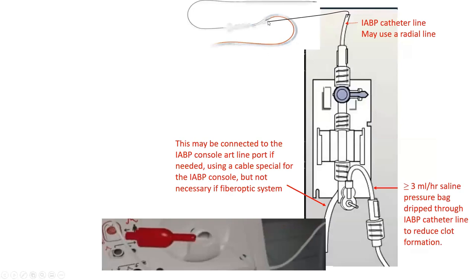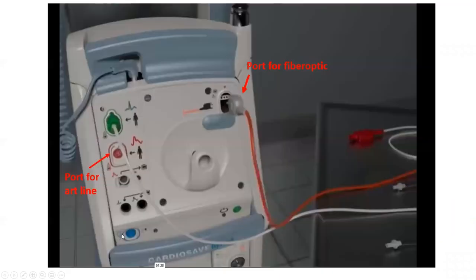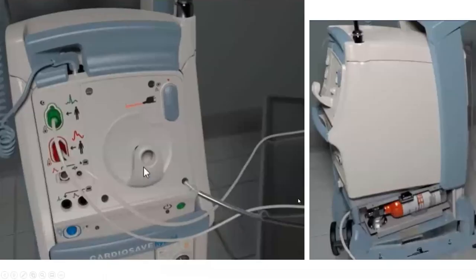And this is an illustration of how you connect this arterial lumen to a line that connects to a transducer, and that's connected to a heparin saline bag that is dripped at a few milliliters per hour. You don't have to connect it via this cable to the console, but you can. And even if you connect it, again, if you have a fiber optic, the balloon pump console will default to using the fiber optic. And you can use the same setup here with a radial line. You connect a radial line to this transducer and to a heparin saline bag, and you connect it via a cable to this back port. You need to know those for troubleshooting.